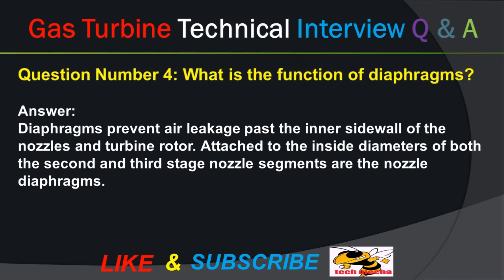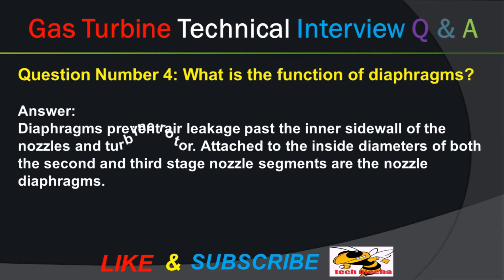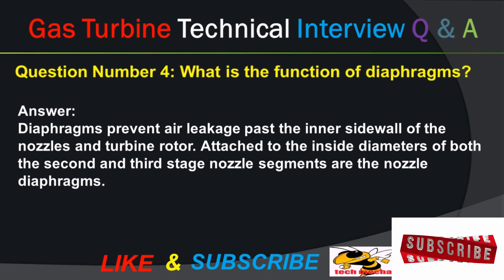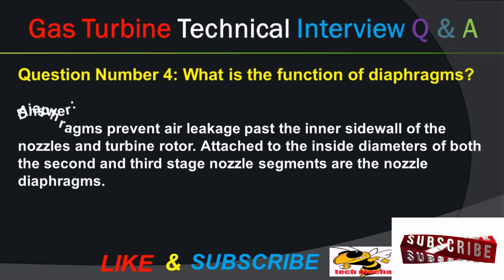Question number four: what is the function of diaphragms? Answer: diaphragms prevent air leakage past the inner sidewall of the nozzles and turbine rotor. Attached to the inside diameters of both the second and third stage nozzle segments are the nozzle diaphragms.